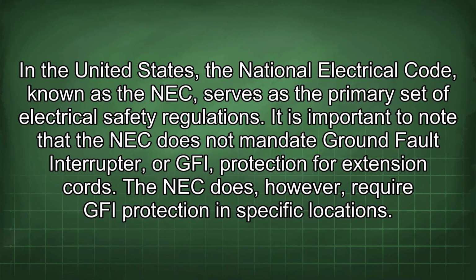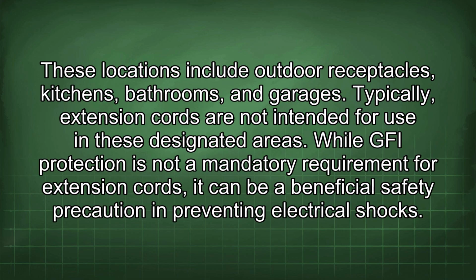In the United States, the National Electrical Code, known as the NEC, serves as the primary set of electrical safety regulations. It is important to note that the NEC does not mandate ground fault interrupter, or GFI, protection for extension cords. The NEC does, however, require GFI protection in specific locations. These locations include outdoor receptacles, kitchens, bathrooms, and garages. Typically, extension cords are not intended for use in these designated areas.